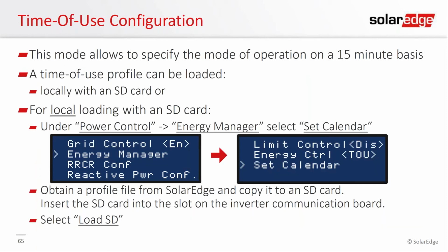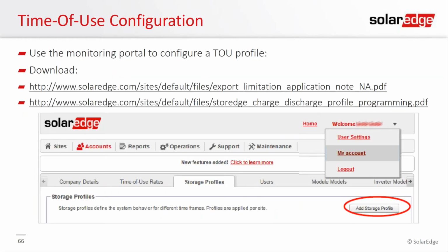So you can set a time of use profile using the inverter and an SD card. This is kind of a clunky way of setting a time of use profile, so I'm always going to recommend you set the time of use profile through the monitoring portal. And the reason for this is it's a lot more intuitive and a lot easier to use. And if you make an update to the profile, it automatically updates all the inverters with that profile. So for example, if you're in PG&E territory and the time of use window changes from 5 to 8 to 4 to 8, then yeah, you want to update your profile. And if you just update the profile, any site associated with that profile will then have the update. So that's why I always recommend using the portal for that. And I have a couple of guides, links to the guides on how to use the portal to create those profiles.